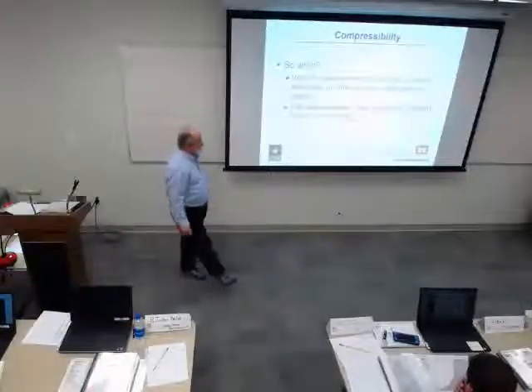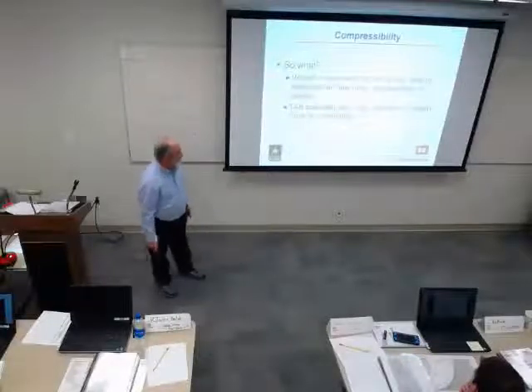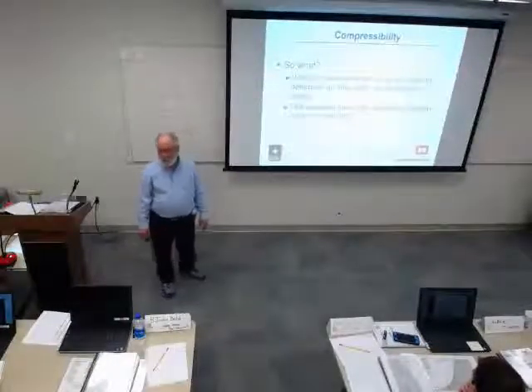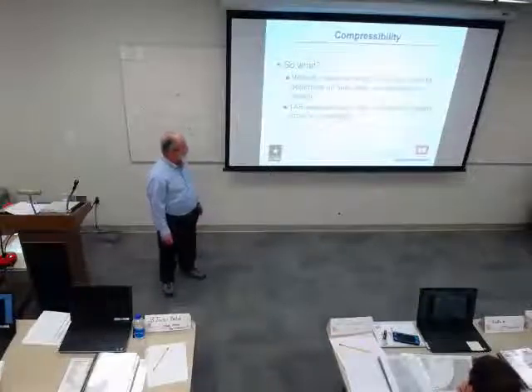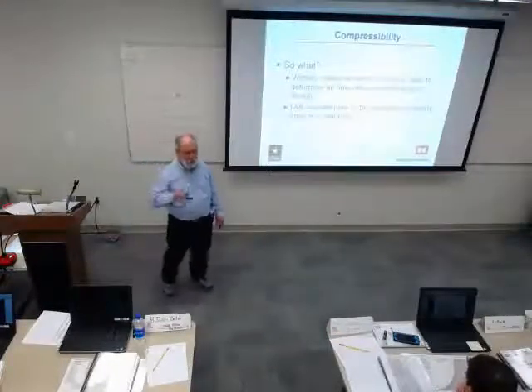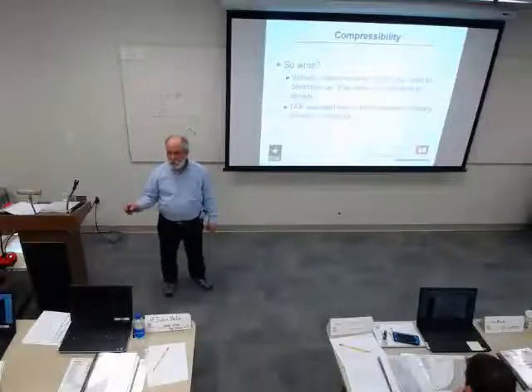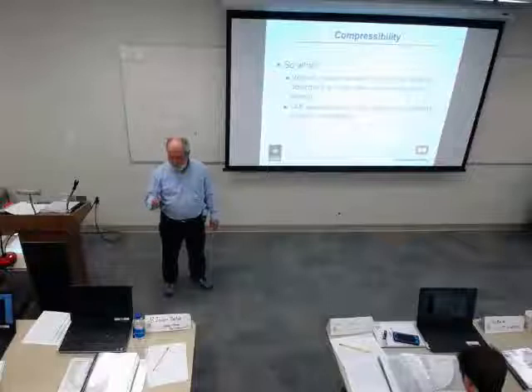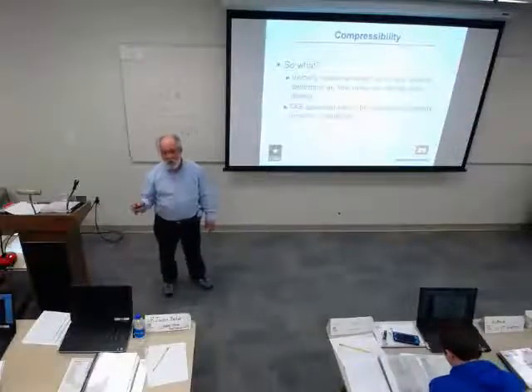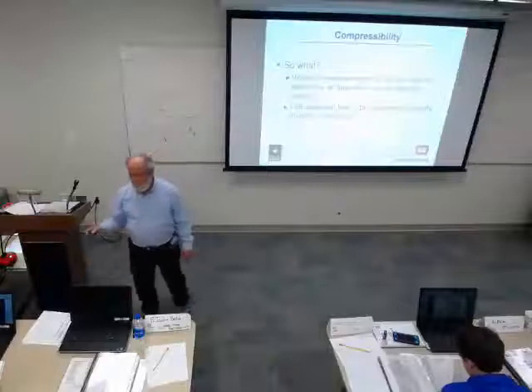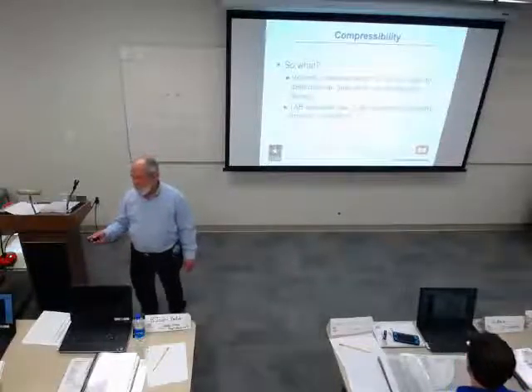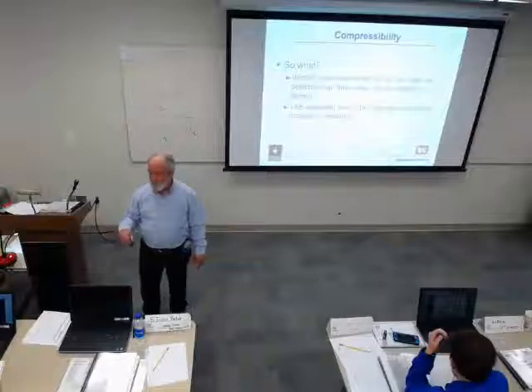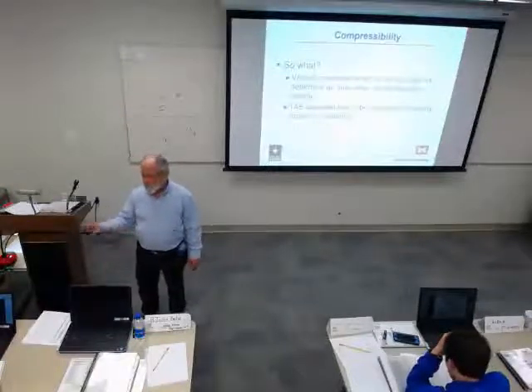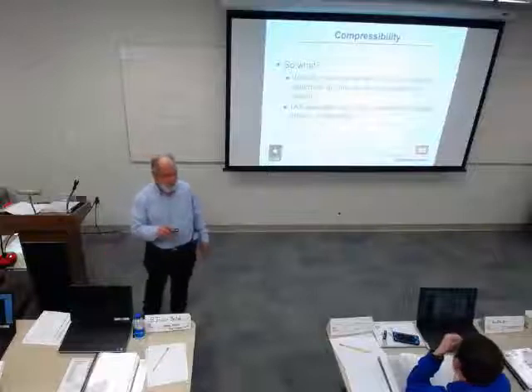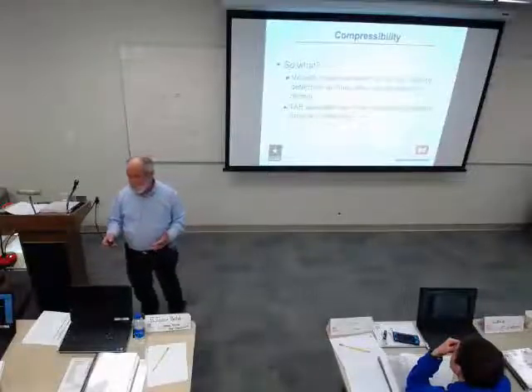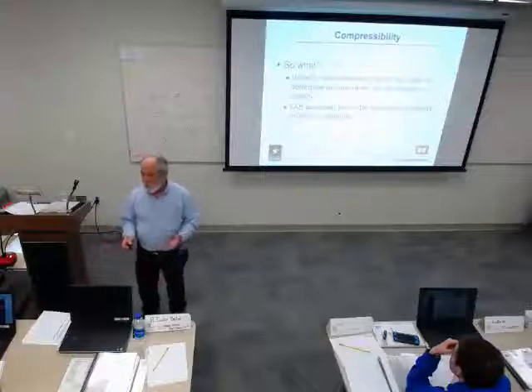So, velocity and temperatures, let's try this. Velocity measurements, which are used to determine flow rates, are sensitive to density. A TAB specialist has to know about that, and you want to be sure that in cases where he's making measurements using instruments, he's included that effect. It might be that for the conditions he's considering, he can use standard conditions and be okay. What you're going to find is that if you're up where the altitudes are higher, you're always going to have to have him do something. In areas closer to standard conditions, not so much. And the same thing applies to temperature.